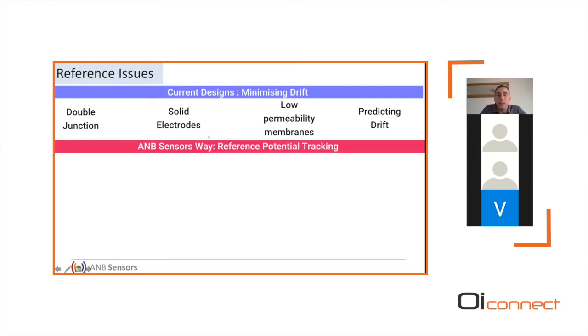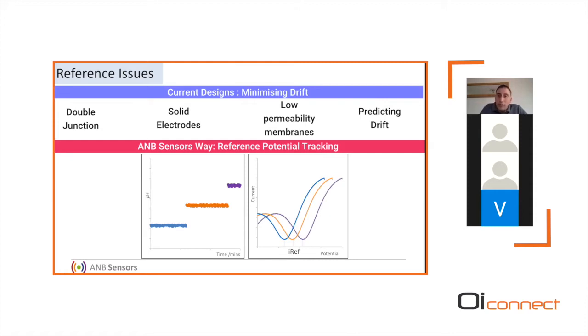We've tackled it in a slightly different way. We said, well, we know drift is going to happen. We're going to look at tracking the drift. So in a conventional pH sensor, you can have a pH change with time, but is that a real pH change or a drift system? Inside our system, we have a way of checking the reference potential.